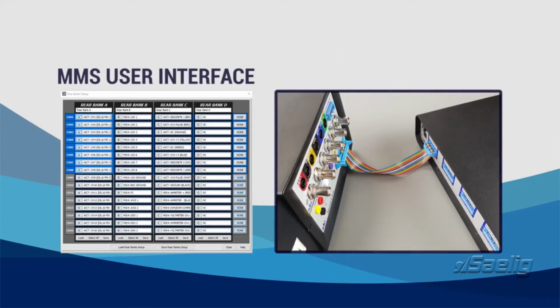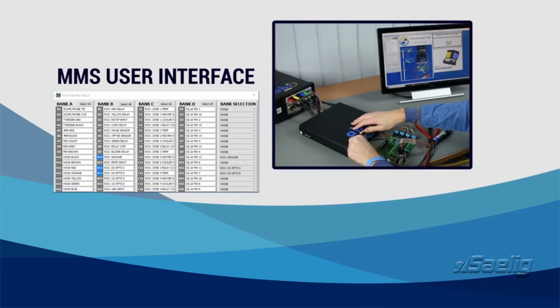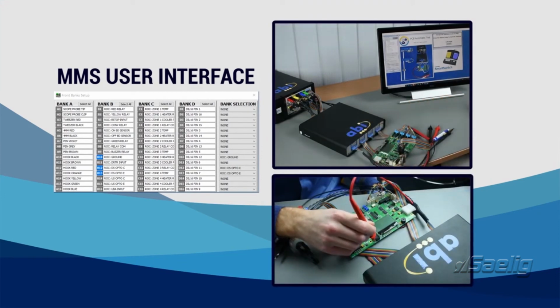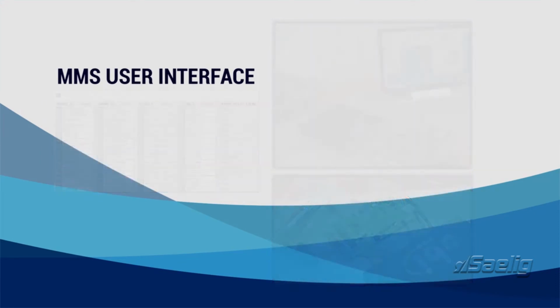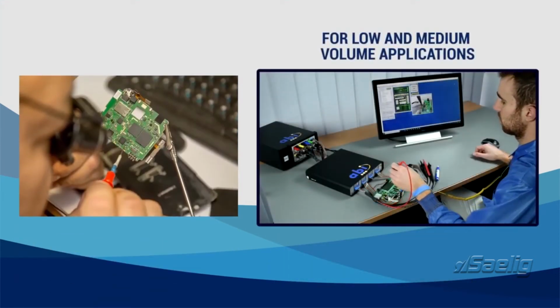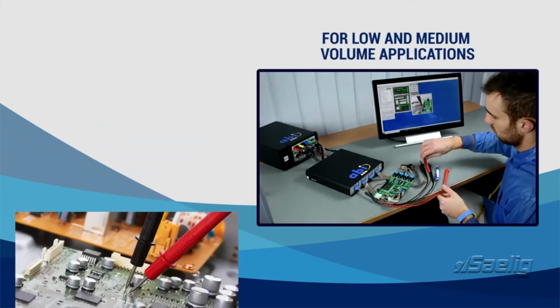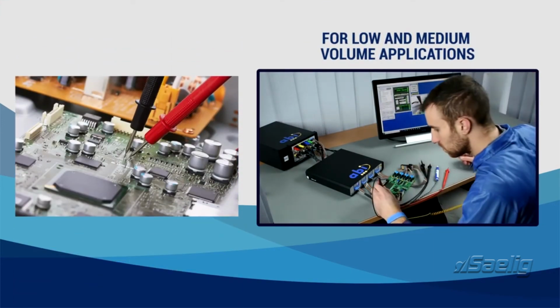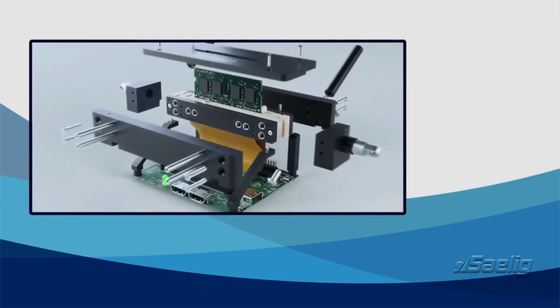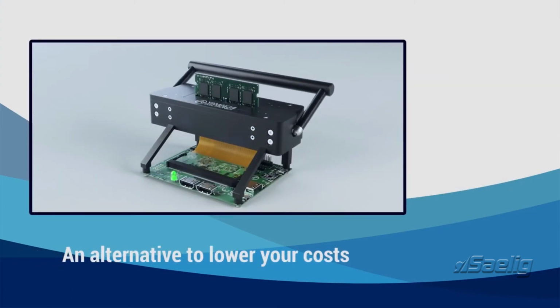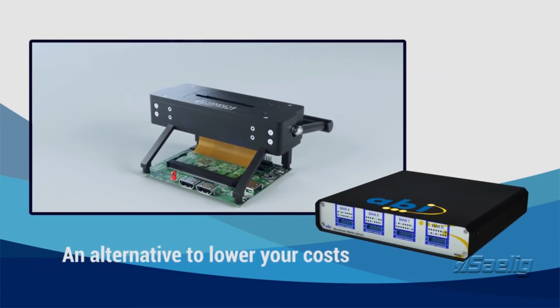In each step, 16 unique paths can be created between the instruments connected to the rear of the MMS and the accessories, probes or test fixture plugged into the front of the unit. With ABI's multiplexed matrix switch and the company's user-friendly System8 Automate software, you can easily and cost-effectively automate existing low and medium volume test routines and applications.